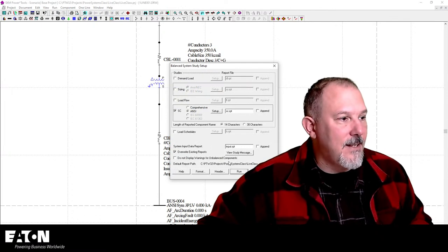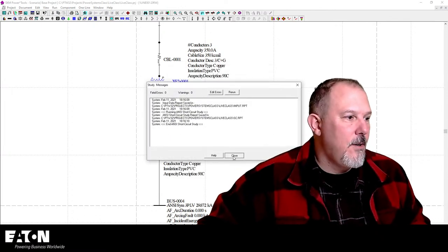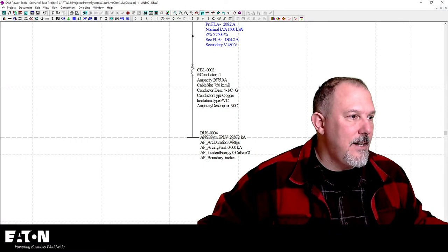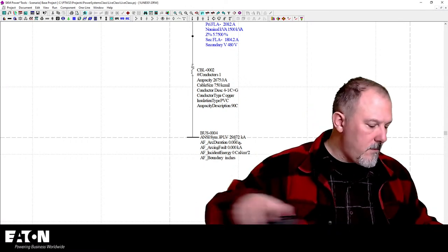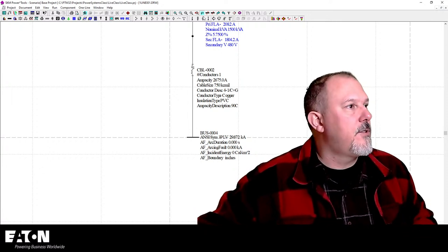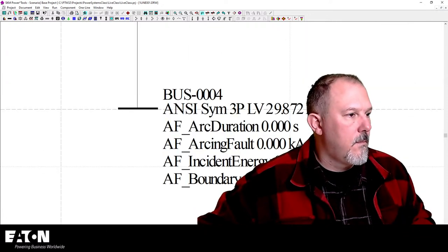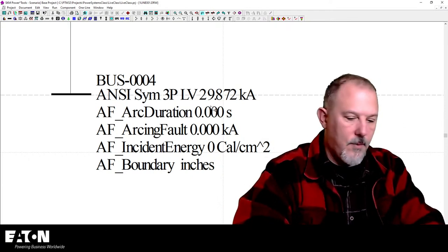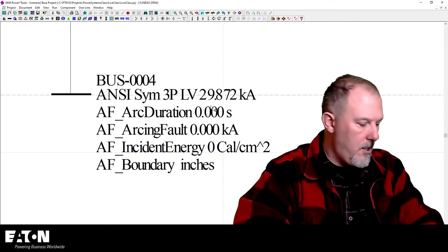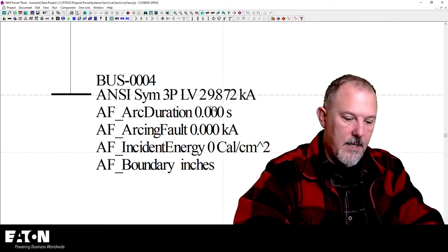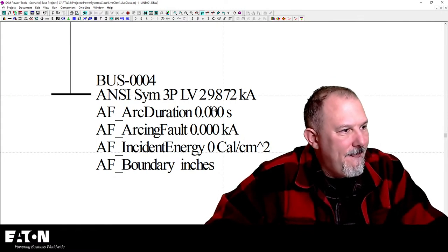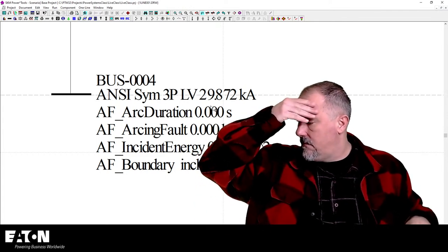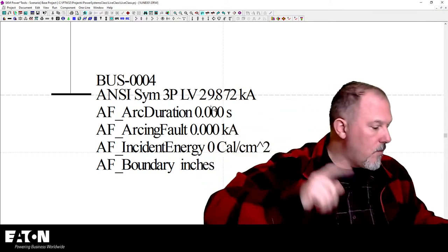Let's run it again. Run, balanced system study, ANSI, short circuit, run. Okay, well, boy, what was our number? 28,775. I got 29,872. Let's just zoom in on that. So there's my number, 29,872, and I did 28,775. Minus, that's 1,000 amps. It should not be that much. What did we do wrong?